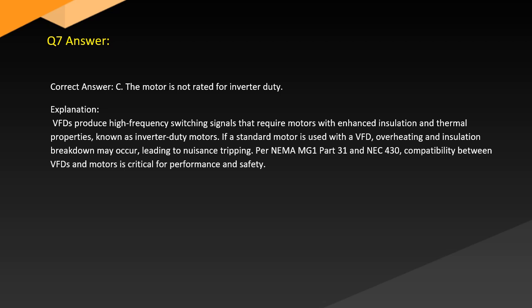Answer. Correct answer: C. The motor is not rated for inverter duty. Explanation. VFDs produce high-frequency switching signals that require motors with enhanced insulation and thermal properties, known as inverter duty motors. If a standard motor is used with a VFD, overheating and insulation breakdown may occur, leading to nuisance tripping. Per NEMA MG 1 Part 31 and NEC 430, compatibility between VFDs and motor is critical for performance and safety.